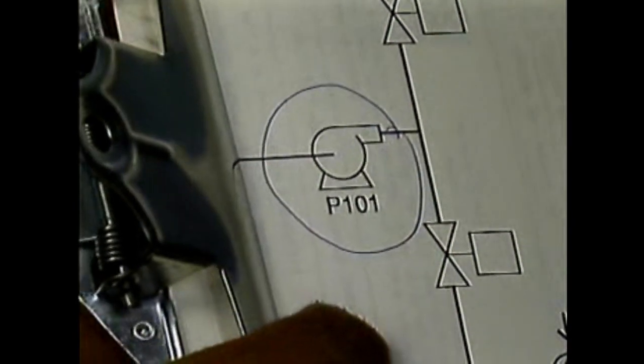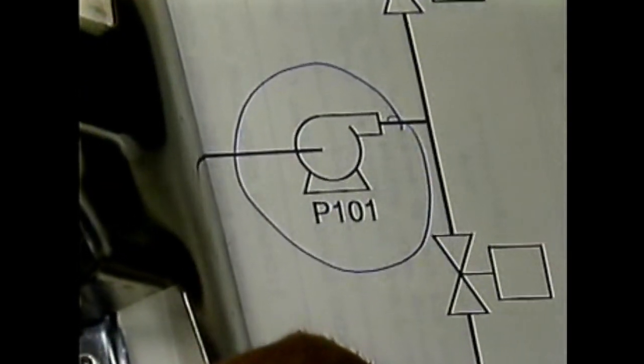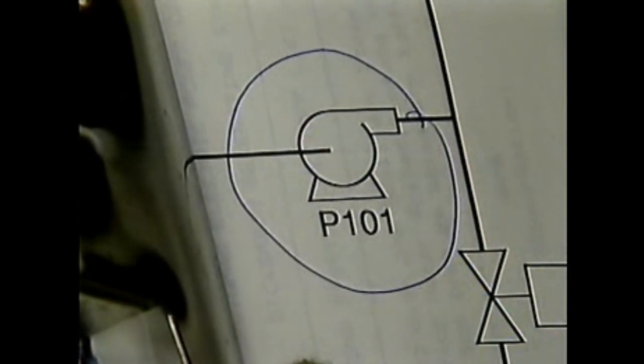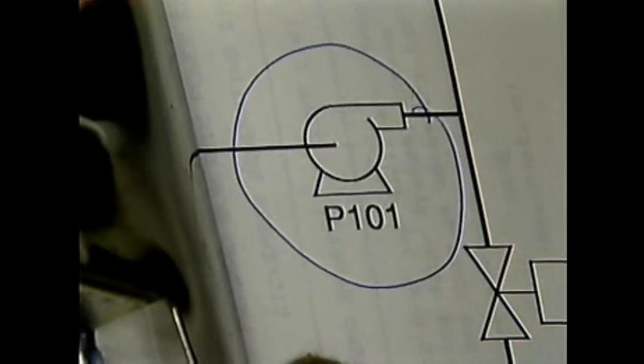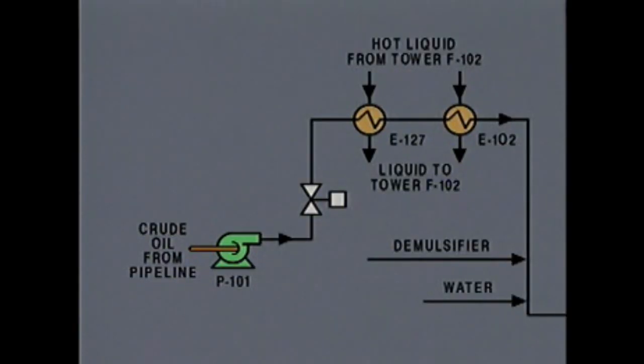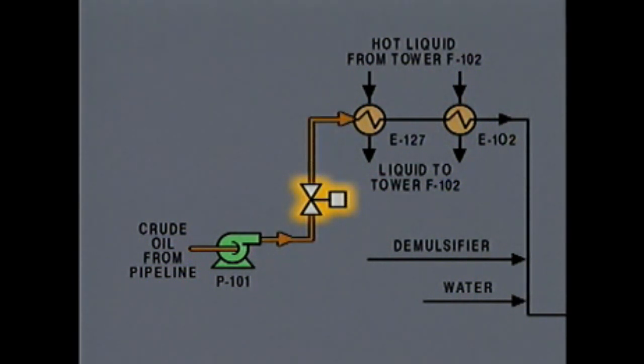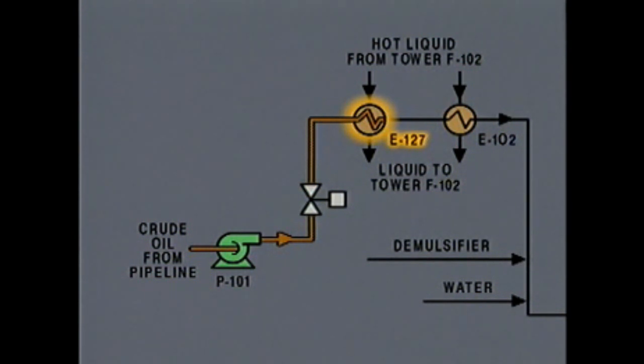Once you locate pump P-101, it's a good idea to circle it on the diagram. Circling components on the diagram as you locate them will help you avoid overlooking components in the system. The next component we come to on the diagram is a pneumatic piston-operated control valve. This valve controls the flow of oil to the tube side inlet of heat exchanger E-127. One way to make sure you have the right valve is to first find the right heat exchanger, which is probably easier to find and is immediately downstream of the valve.